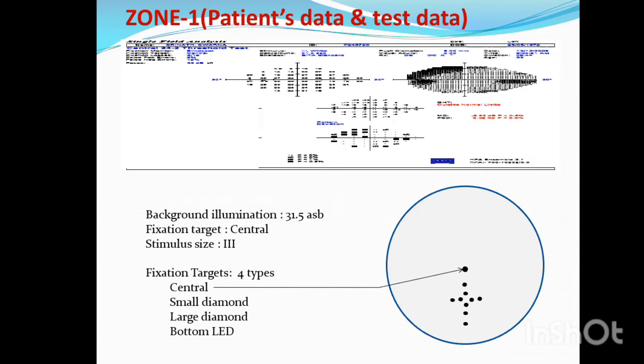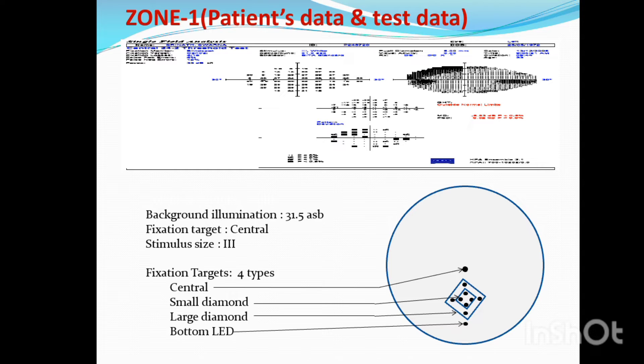We will be able to test the fixation target. The fixation targets are: one is central, one is small diamond, one is large diamond, and one is bottom LED. To test the macular threshold or foveal threshold, we use the small diamond with small stimulus lights and the small rhombus.